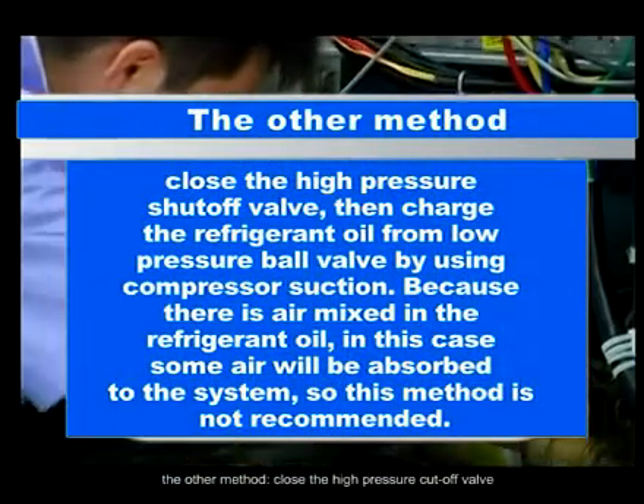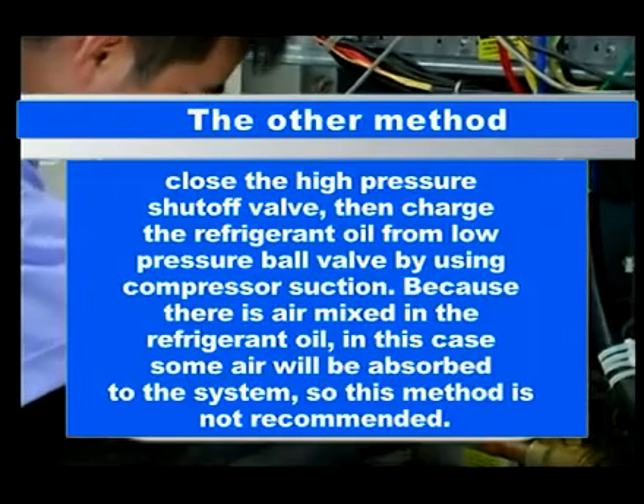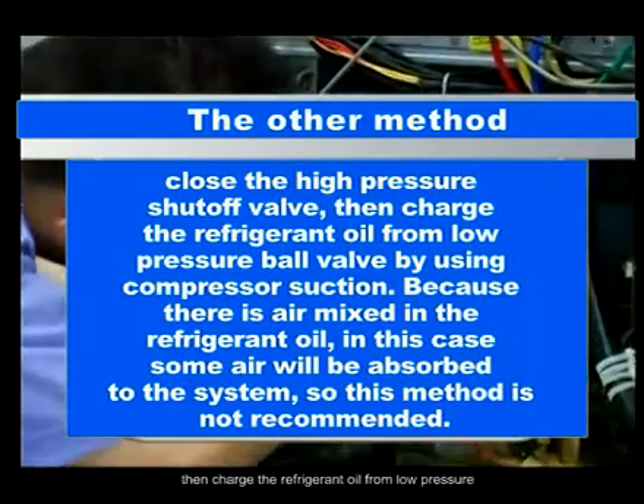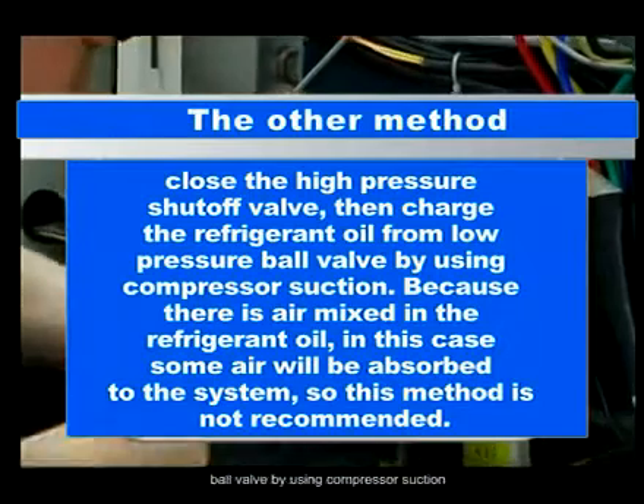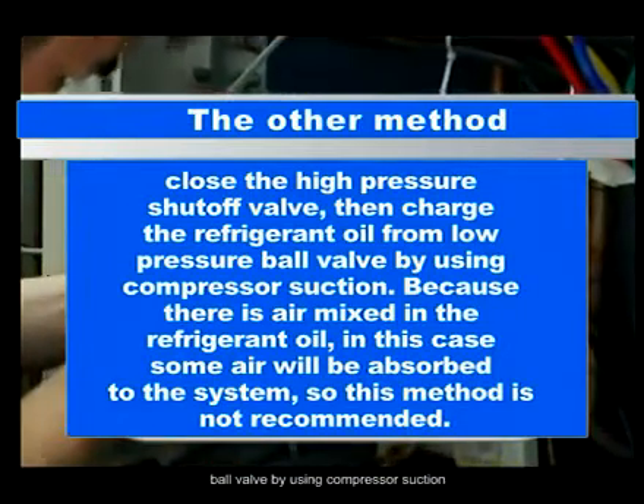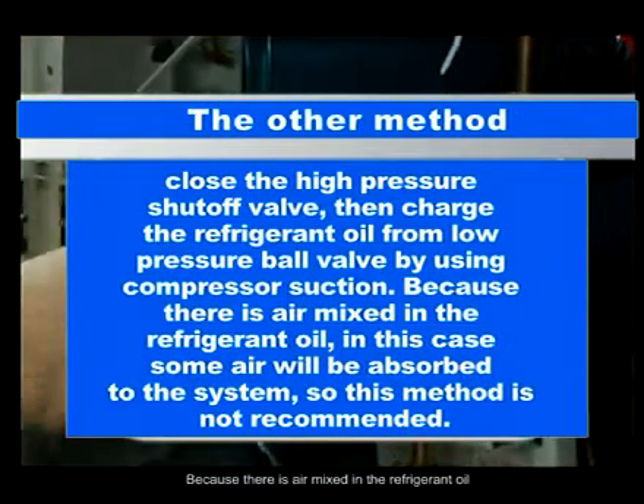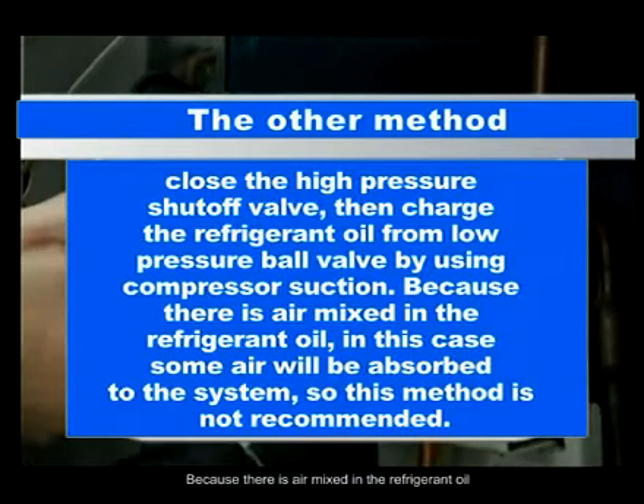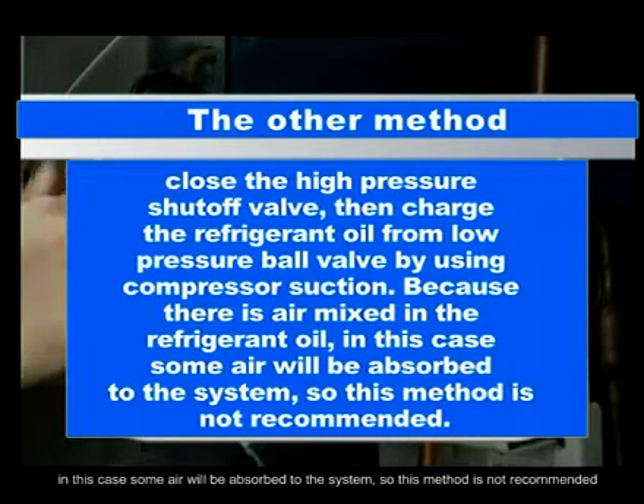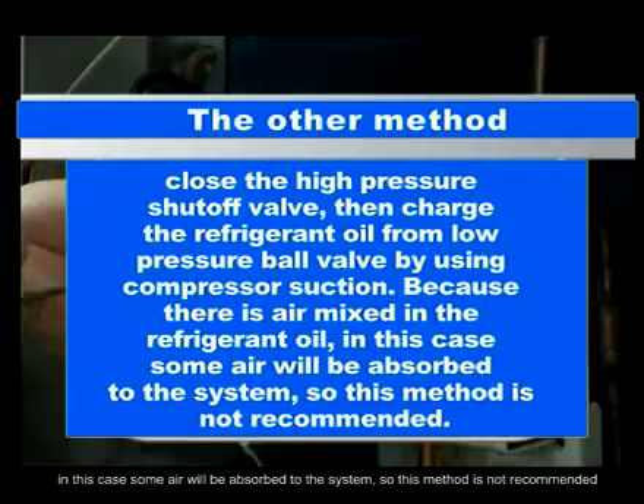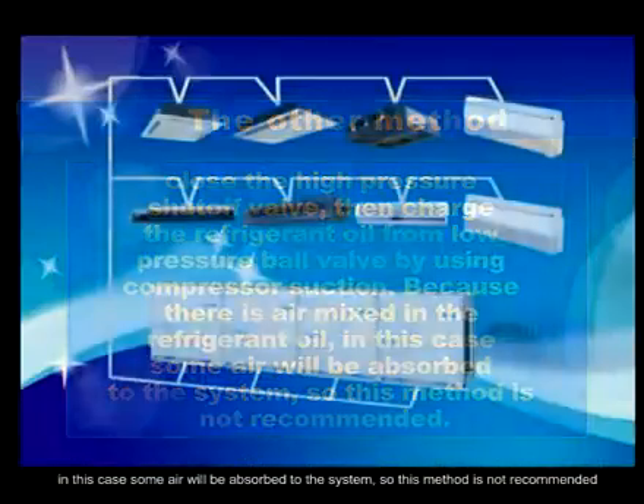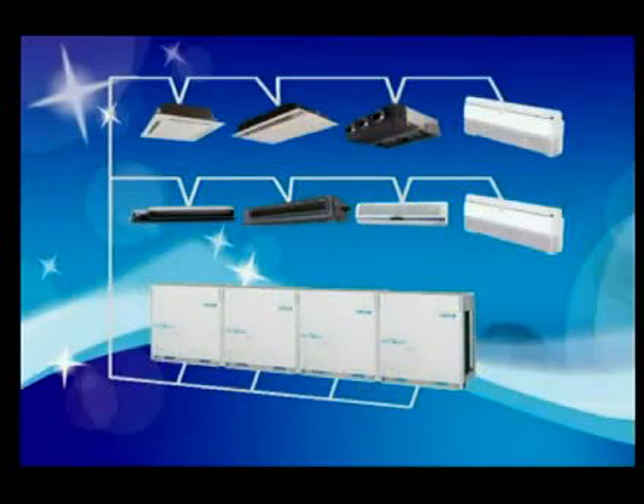The other method: close the high-pressure cutoff valve, then charge the refrigerant oil from the low-pressure ball valve using compressor suction. Because there is air mixed in the refrigerant oil, some air will be absorbed into the system, so this method is not recommended.